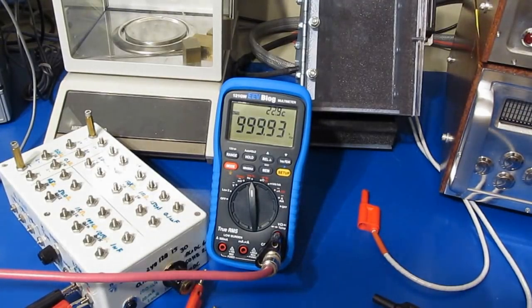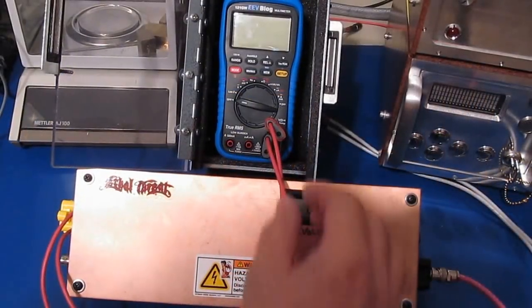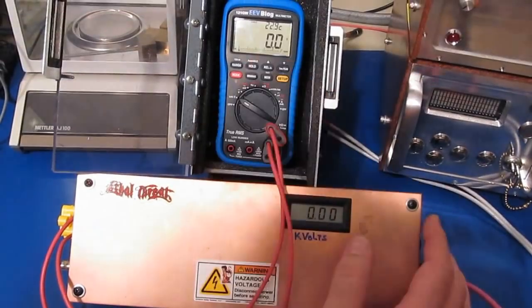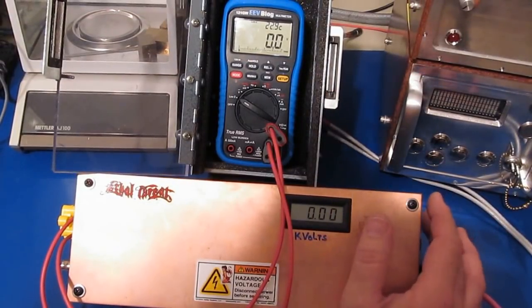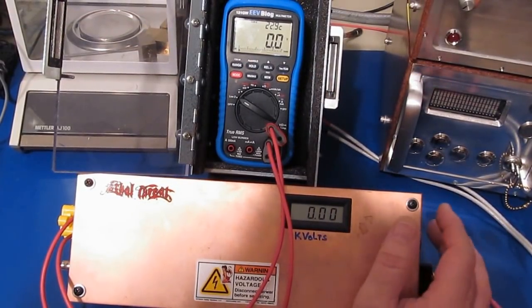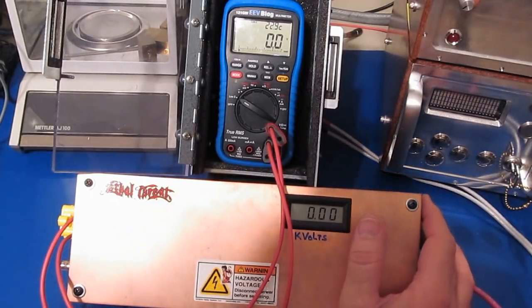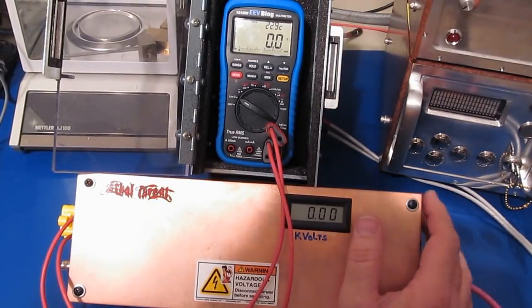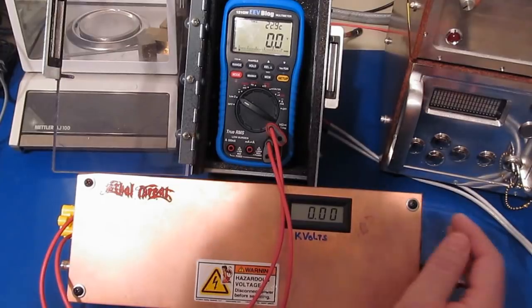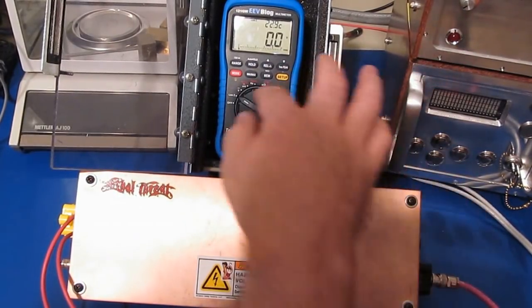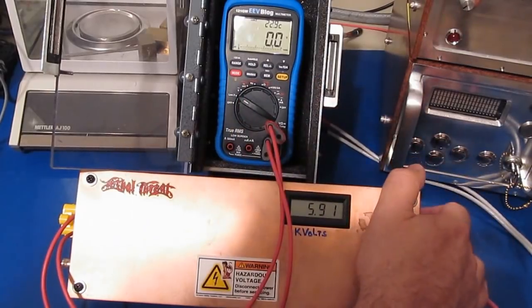See, that is the top end of the meter. Next we'll run our ESD test. This generator will put out about 4,000 volts peak in less than a nanosecond, and it'll also apply somewhere around 15 amps. It's very close to what the IEC standard calls for. And again, I'll be applying 5 transients, both positive and negative, with each mode of the meter.